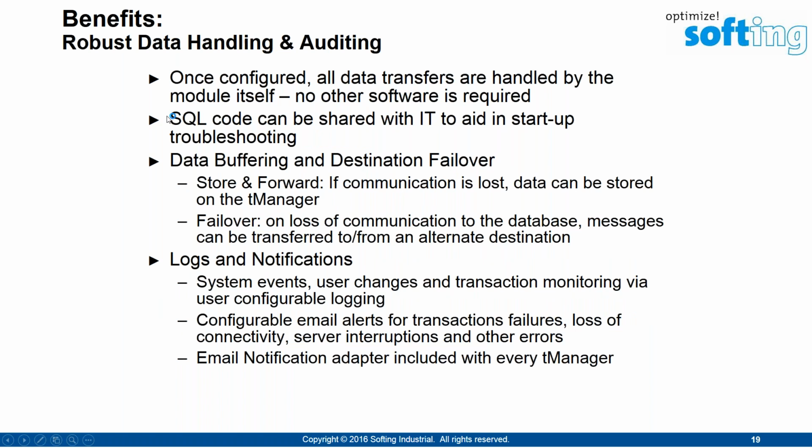Another group of benefits pertains to robust data handling and auditing. Once configured, the module independently handles all the data transfer. Even though you don't have to know anything about SQL statements, once you create a transaction, you can share the resulting SQL statement with the database administrator. When you create the message path, there's a button called SQL statement. You click on that button and you see exactly what the SQL command is, and you can share that with the database administrator to confirm that you're doing the right operation.